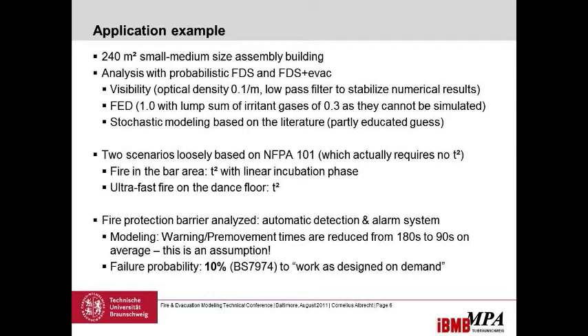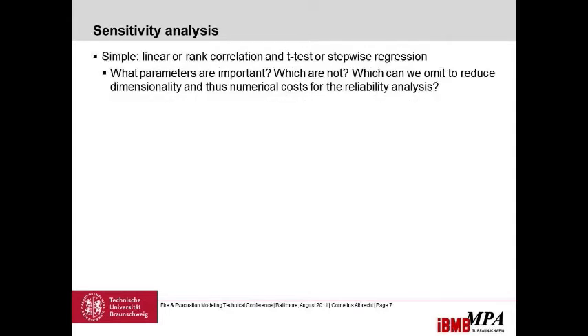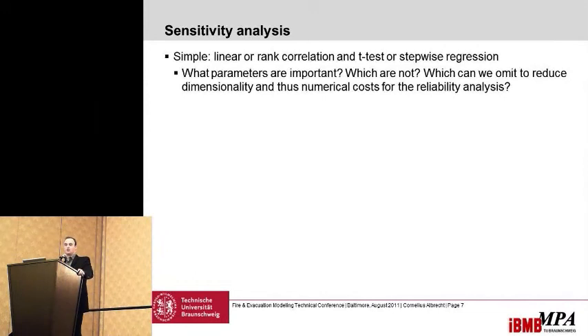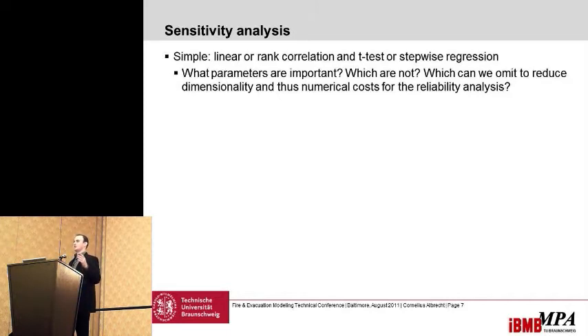The failure probability of the automatic detection and alarm system not working as designed on demand is 10%, as given in British Standard 7974. For the sensitivity analysis, I kept it as simple as possible using linear and rank correlation analysis, then T-tests or stepwise regression. This gives answers to which parameters are important, which are not, and which can be omitted — because reducing the dimensionality of a reliability problem definitely reduces the computational time needed.